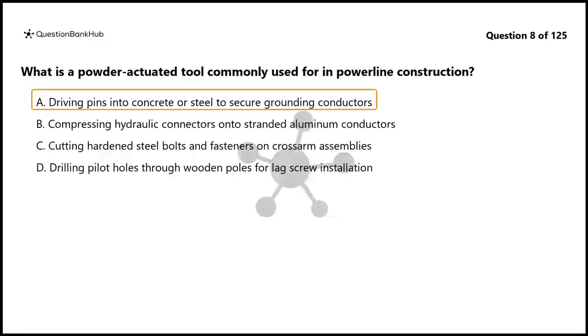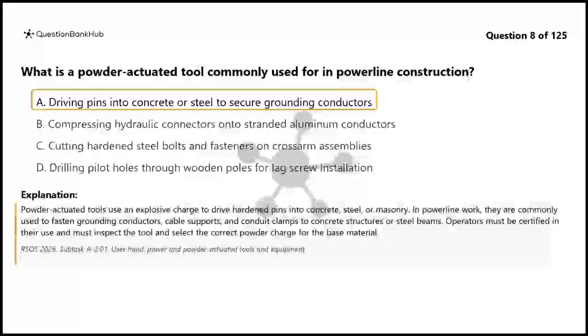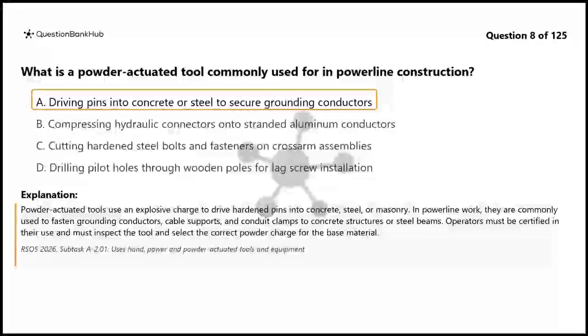The correct answer is A. Powder-actuated tools use an explosive charge to drive hardened pins into concrete, steel, or masonry. In powerline work, they are commonly used to fasten grounding conductors, cable supports, and conduit clamps to concrete structures or steel beams. Operators must be certified in their use and must inspect the tool and select the correct powder charge for the base material.